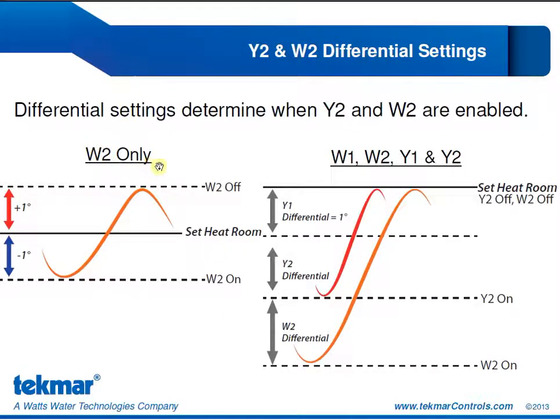I want to look at some other settings that are not essential settings but will enhance the performance of your system. The first we're going to look at are the Y2 and W2 differential settings. If W2 is the only source of heat, so for an example would be when we're using that W2 relay to control a single stage of furnace, then you cannot specify the differential. The differential will be fixed, and it is 1 degree below set heat room and 1 degree above set heat room. So W2 relay will turn on when we are 1 degree below, and it'll turn off when we're 1 degree above.